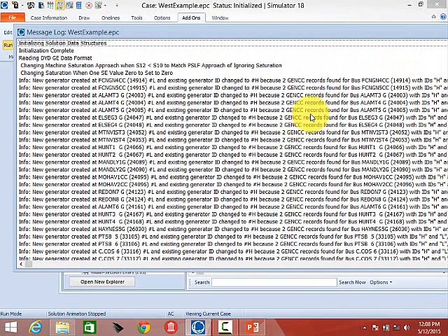One issue, and this is covered in the slides, is there's often a difference between how generators are modeled in the PowerFlow and how they're modeled in Dynamics, particularly generators that have a high-pressure steam model and a low-pressure steam model. In the PowerFlow, these units tend to be modeled as one generator.